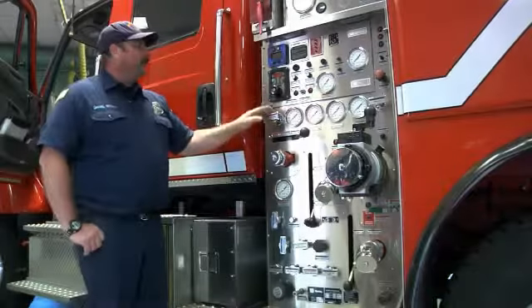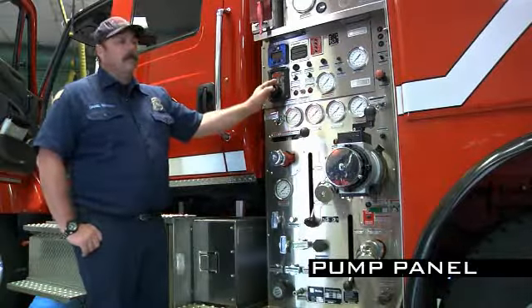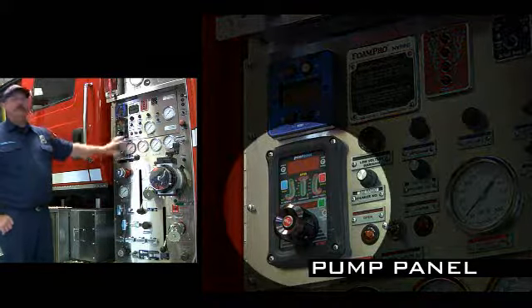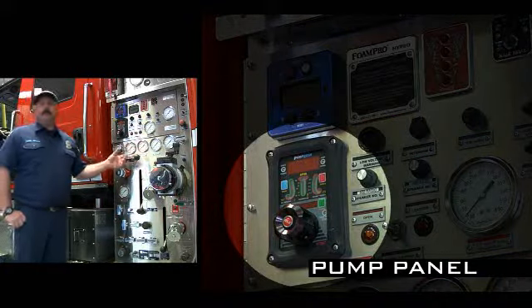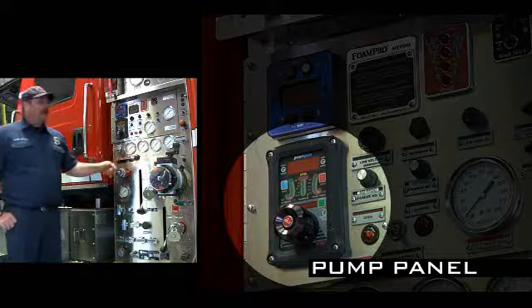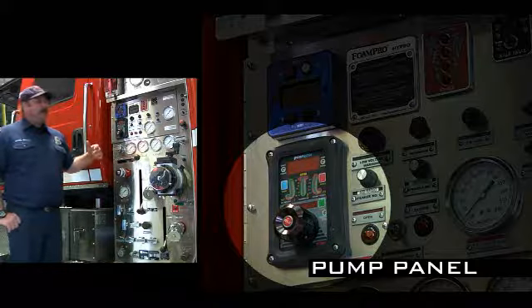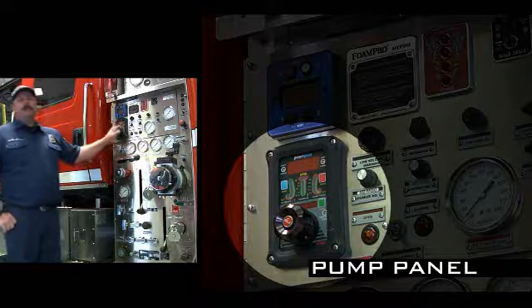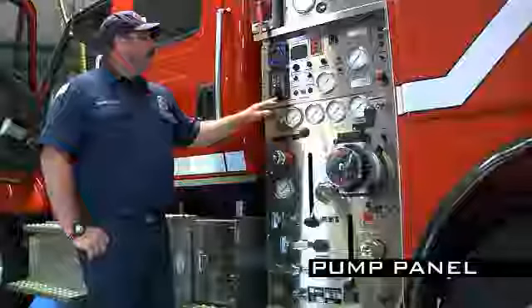Here at the pump panel, we're talking about our pressure governor. It's a Pump Boss model. It does slowly move up and down, but it has multiple transducers within the pump, and those transducers are sensitive to being blocked by silt or sand. Okay, so if you're in the high desert or you're getting water from an unclear water source, there is the possibility that this thing may or may not continue to respond appropriately.